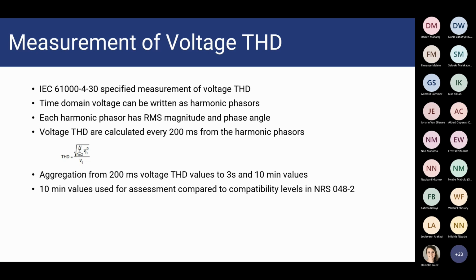So it's the square of your individual voltage phasors up to the 50th harmonic, and then the sum of that, and then the square root of that divided by your fundamental voltage. So that's how voltage THD is calculated. And it's aggregated from 200 milliseconds. That 200 millisecond voltage THD is then aggregated to 3 second and 10-minute values, which are then used for your assessment. So the 10-minute values are compared to the compatibility levels, which are specified in the NRS 048-2.